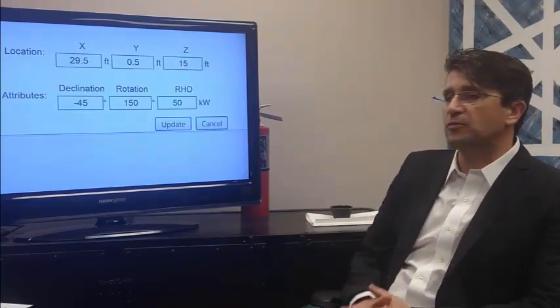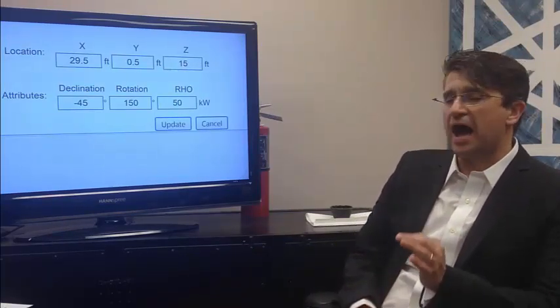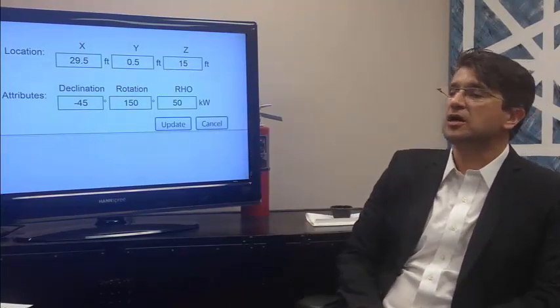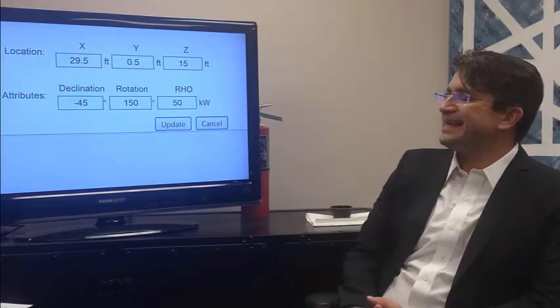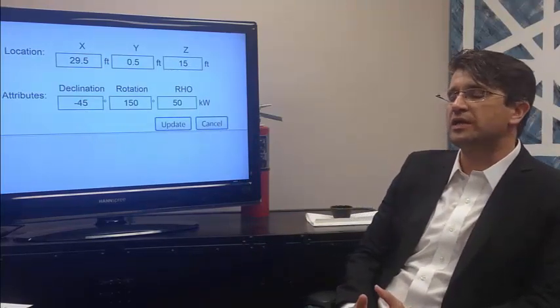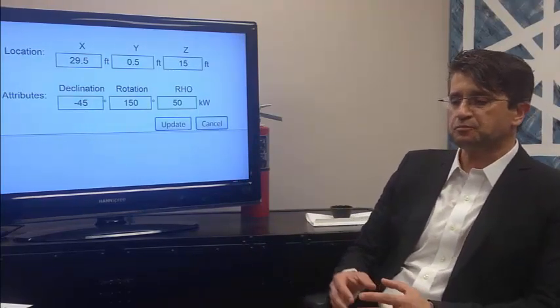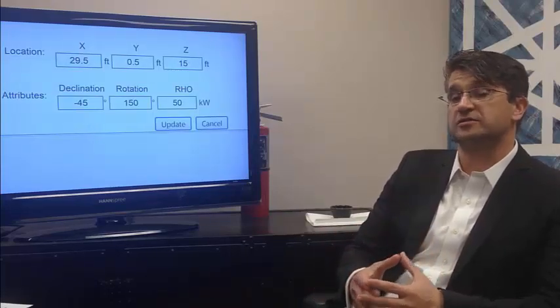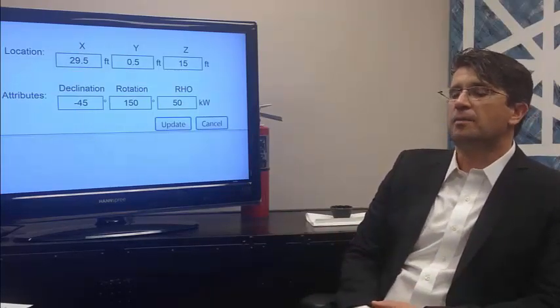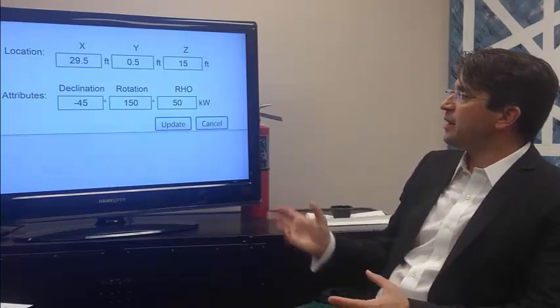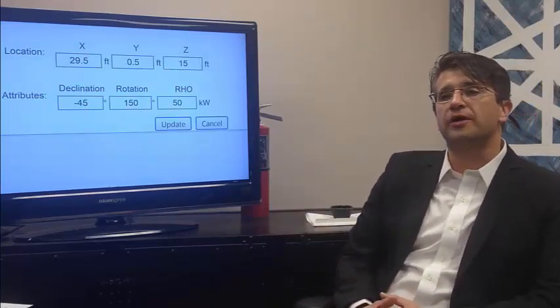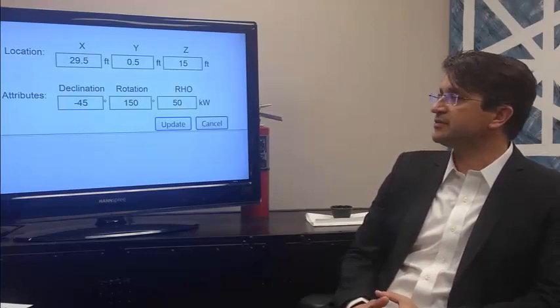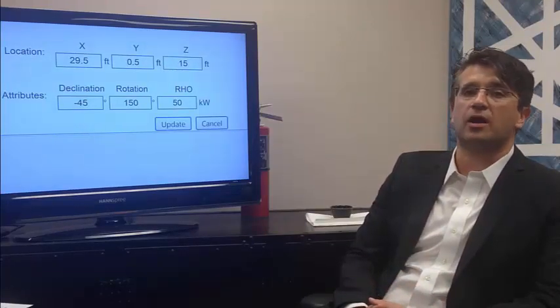And the parameter that we use to define how big of a fire do I actually want to detect is the radiant heat output. So radiant heat output is something that we can calculate using a lot of quantitative consequence analysis equations and tools. But in general, that number is going to come from corporate fire and gas philosophy documents that are going to define how big of a fire that I want to detect.